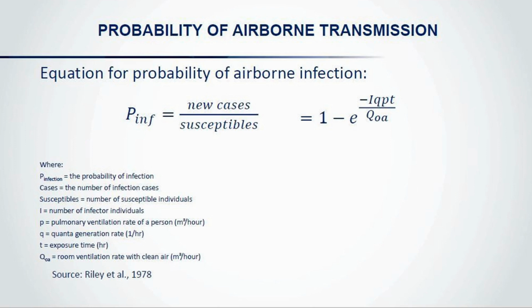From that, we can calculate a required ventilation rate equivalent to the transmission rate, R0, for any limiting disease transmission rate for any specific disease. So if I say I can tolerate a 1% or 5% transmission rate, I can put that into R0. I can use disease Q, the quantum generation rate, and plug in TB, different strains of TB with and without treatment, COVID, etc. I can put in the number of occupants, the size of the room, and the exposure time - if it's a waiting room of 4 hours, we can plug that in there.